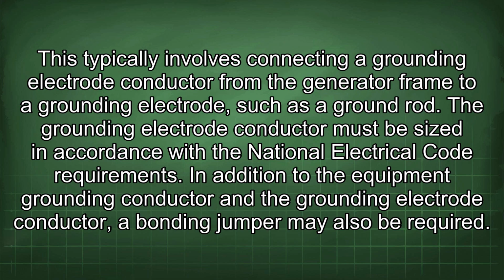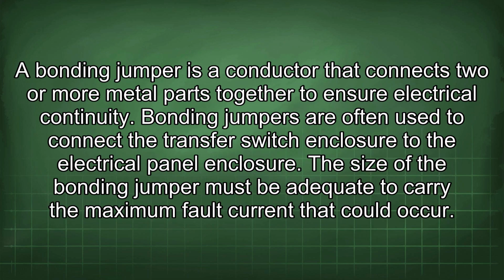In addition to the equipment grounding conductor and the grounding electrode conductor, a bonding jumper may also be required. A bonding jumper is a conductor that connects two or more metal parts together to ensure electrical continuity. Bonding jumpers are often used to connect the transfer switch enclosure to the electrical panel enclosure. The size of the bonding jumper must be adequate to carry the maximum fault current that could occur.